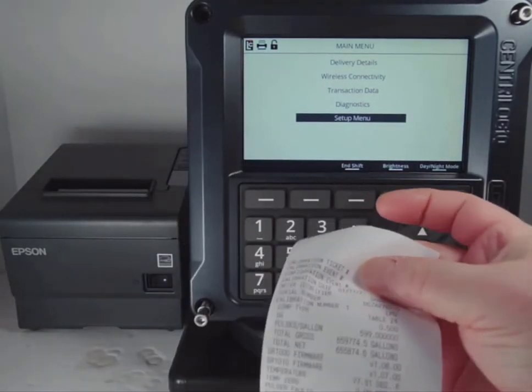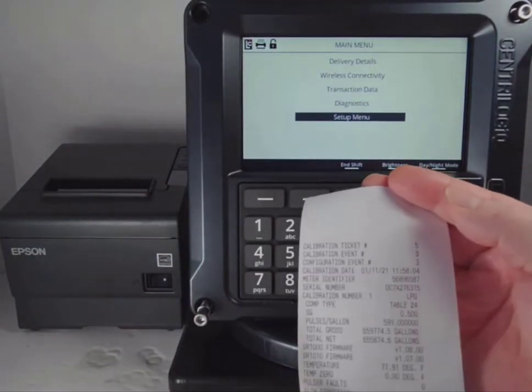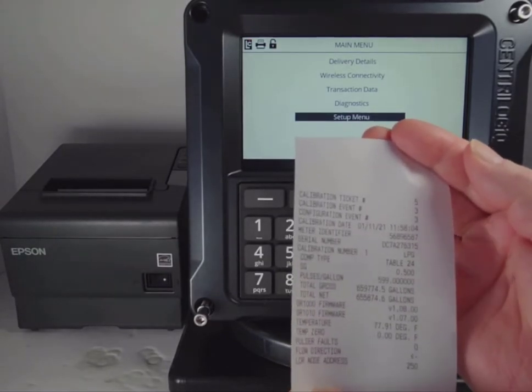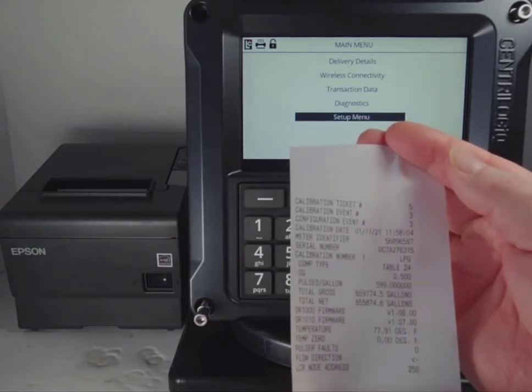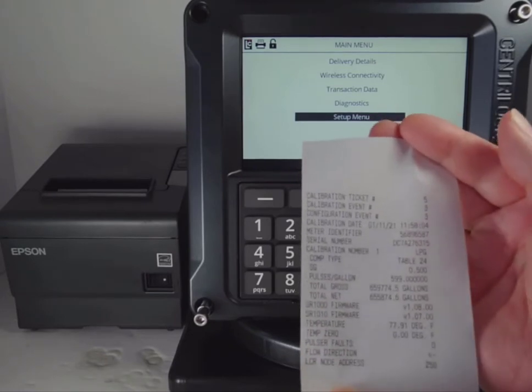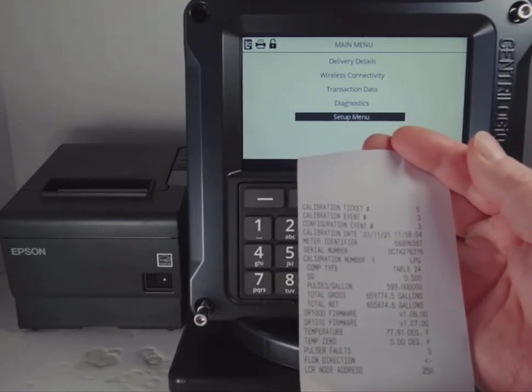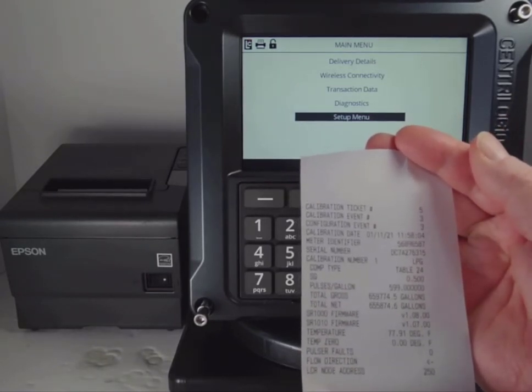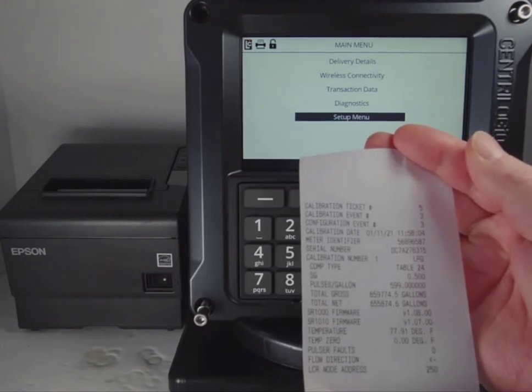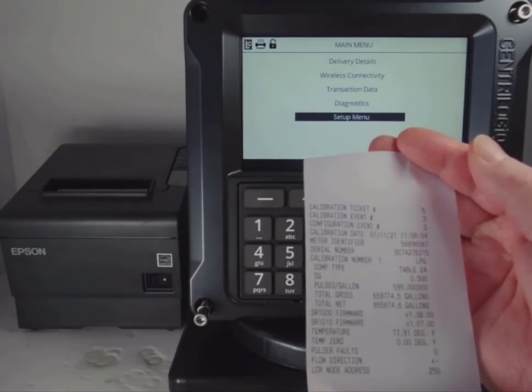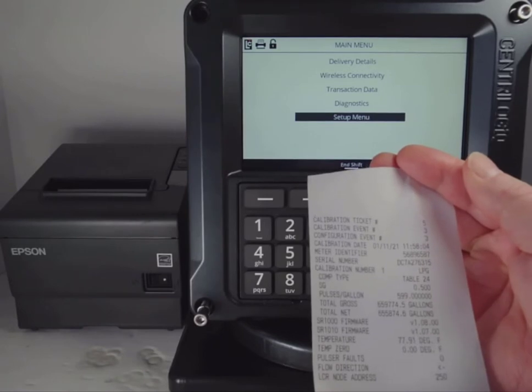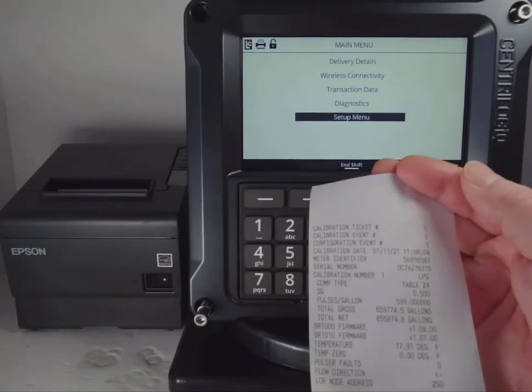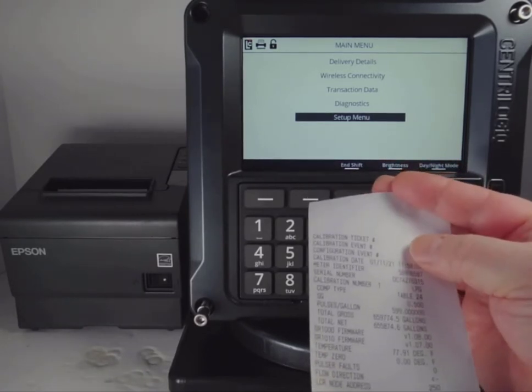This can be an important tool when setting up the LCR.iQ later. We do have a save and load configuration feature that will save this information. However, it never hurts to have a calibration ticket as backup. This ticket will print when you enter calibration mode if you have a ticket printer connected and a ticket in place. If you retain this for your records, it may come in handy later on if needed.